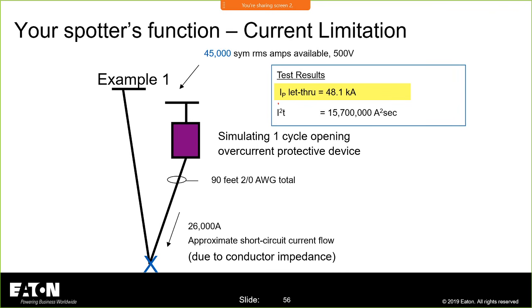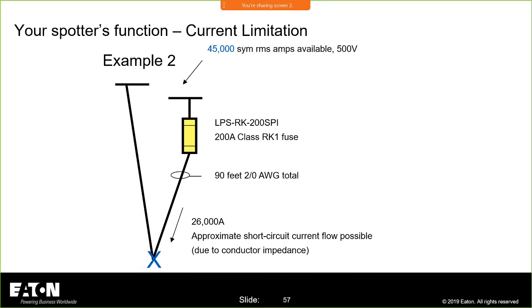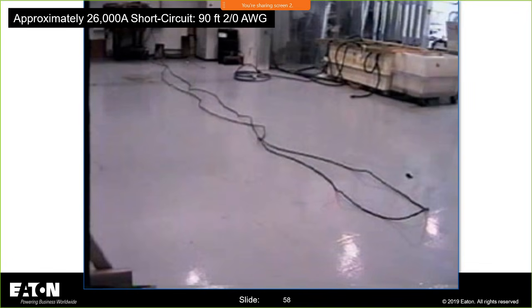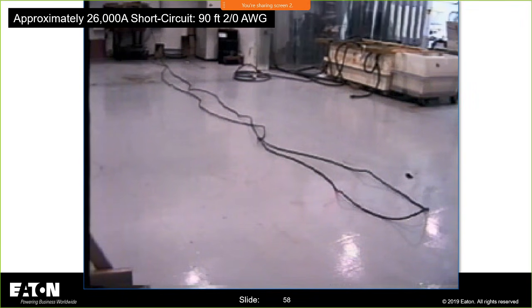Now, to show what a current limiting device does for us in a power distribution system, we put a 200 amp Class RK1 fuse in the picture. The same exact scenario, 26,000 amps, 2-aught conductor, and we do the exact same test, and now you'll see the results of that test. I don't know if you saw that, but watch it again, and watch right in here to see that move, and you'll notice how there is little to no movement in that conductor.